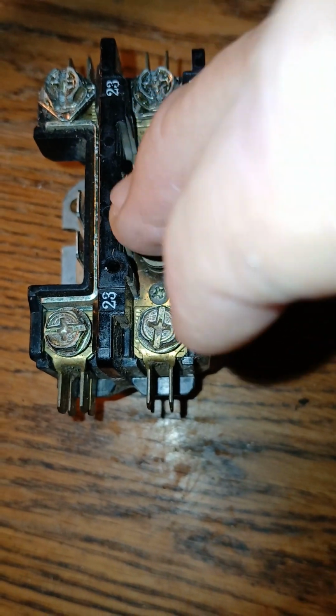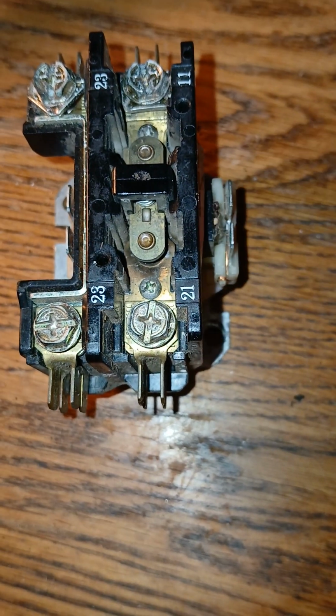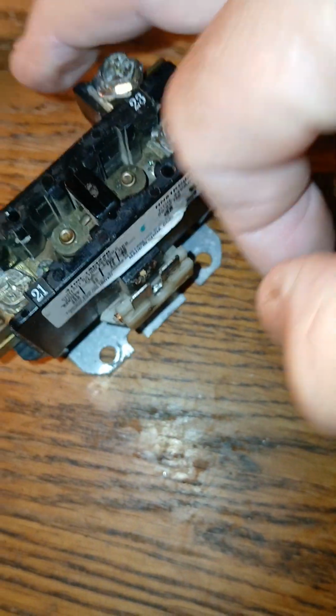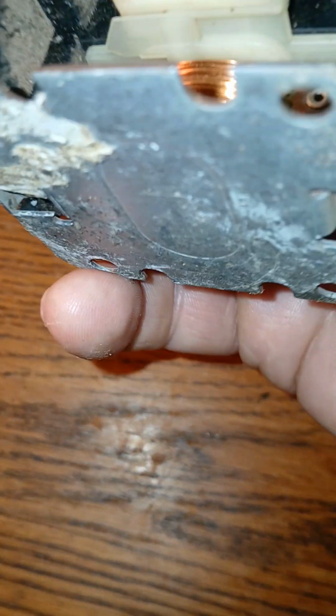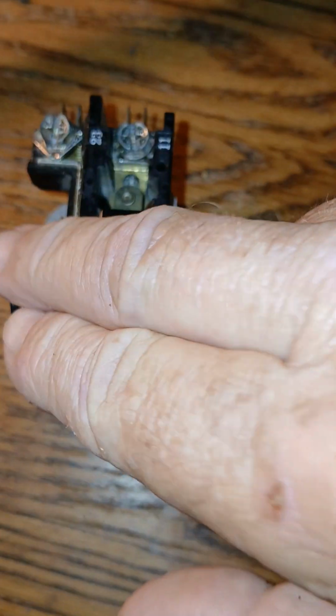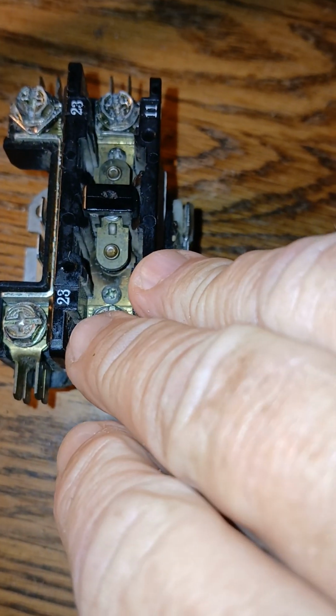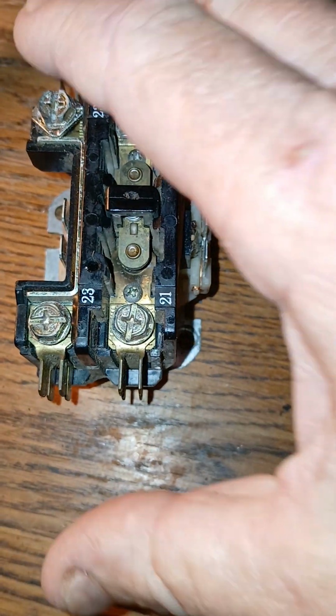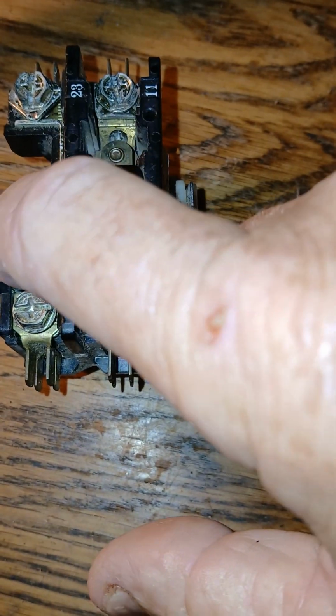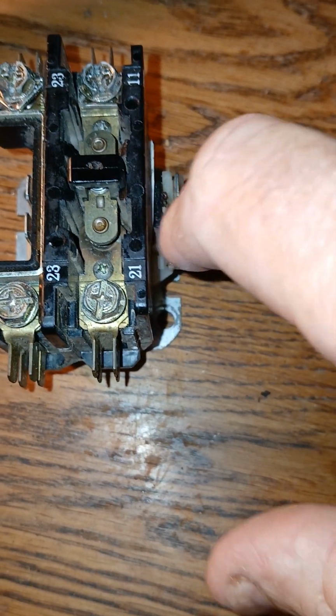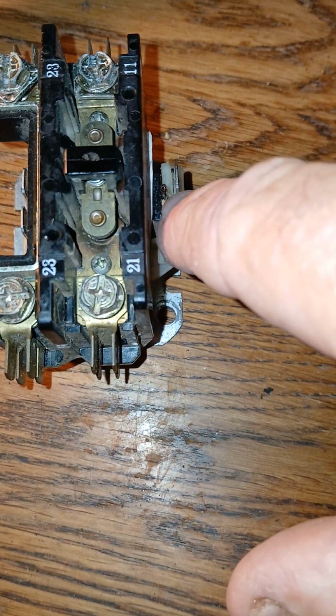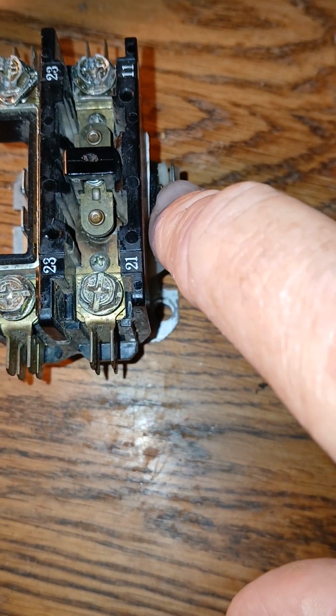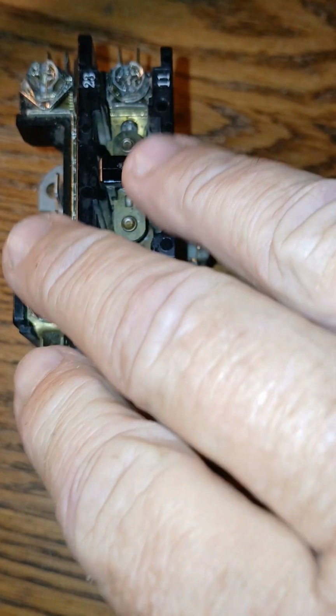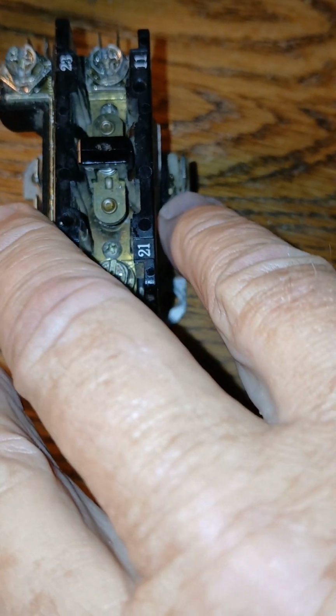Now one may ask, well, what causes this plunger to pop in? It's simply on the side, as one can see, there are terminals on the side, and these terminals on the side are low voltage terminals. There's a coil under here, and this is for low voltage. One plug-in would plug on one side, one plug-in would plug on the other side. So when this becomes energized, say, for instance, if you were calling for cool and you had a yellow wire and a blue wire, or some people actually come out here with a red wire and then a blue wire. The blue would be your common, the yellow would be your hot, or the red would be your hot. But I think the red would tap on somewhere under the yellow in the air handler, or somewhere it would come from the thermostat.